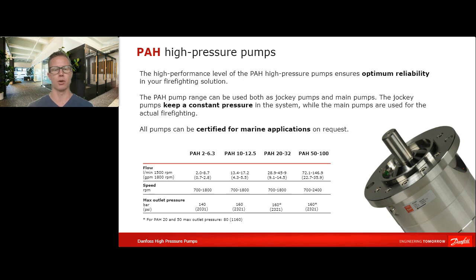Then when we're talking about other firefighting related certifications, mostly, when we're talking about high pressure water mist, they are on a system level. So they are not on each single component as such. It's a complete system certification. We can, however, of course, for the sake of our pumps, provide the documentation that is needed to support such a certification. Could be like FM or the German VdS, that sort of thing. But it is a task that is being handled by the firefighting OEMs, and then we support it.